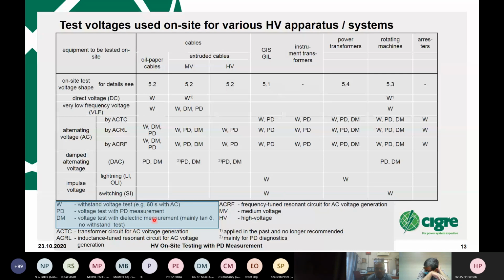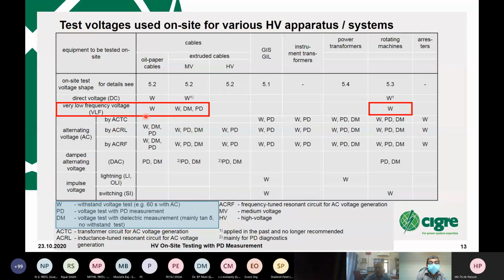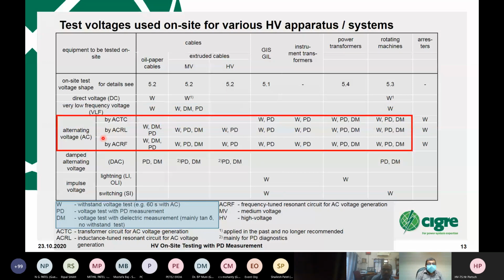And now you can see these abbreviations standing for frequency resonant test system and transformer, and you will see it on the next slide. Now it's important to have a first view. For example, the very low frequency, 0.1 Hertz sine wave, is allowed for oil paper cables, medium voltage, as a withstand test, and also for medium voltage up to 31 or 32 kilovolt. And of course, as a diagnostic method and with PD. Diagnostic means after the system is in operation and you'd like to have maintenance and so on. It's also used, defined in the standard and accepted for rotating machines.